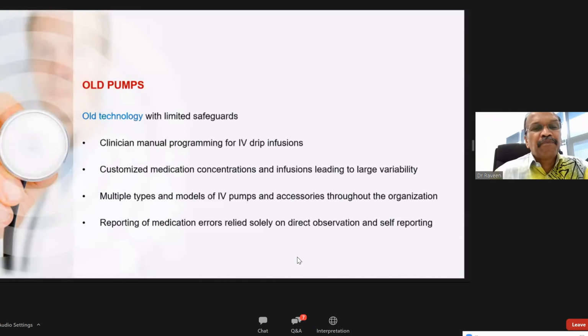So if I want to give 3 milligrams per kg body weight to run over 1 hour, I need to calculate how much is 3 milligrams, and how many mils I need to run at, before I key the data into the pumps. Or in the labor room, if you want to augment the labor, we count the number of drops, saying 30 drops equals 1 ml, that kind of calculation we used to do. But technology has come up so well that we don't have to do these calculations. Everything is programmed into the pump.